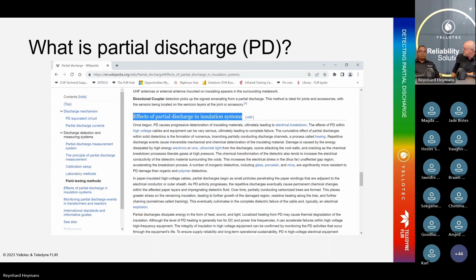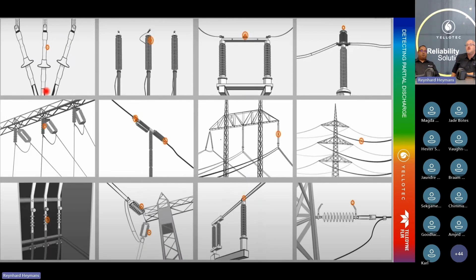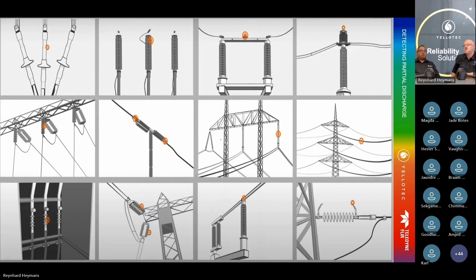If you look at it, partial discharge can actually occur phase to phase, phase to ground. It can occur in solid insulation, air bubbles within a transformer, and the gas around an electrode. So partial discharge can occur in all of these places. And just some quick examples for those of you that have got substations or worked on high voltage lines. You start to see that these are examples or points where partial discharge can form. Here you've got a termination, discharging through the actual insulation. On the far right, you've got discharge on the actual line.